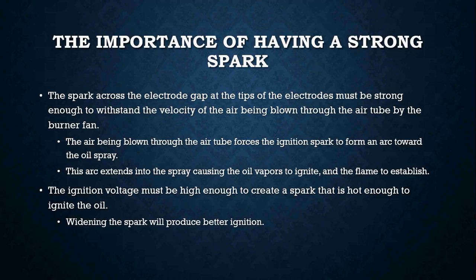Okay, the air being blown through the air tube forces the ignition spark to form in an arc toward the oil spray. So really what we want to do is use the air that's coming down the air tube to almost push that spark into that spray of oil so that we can actually ignite it. So that arc extends into the spray, causing the oil vapors to ignite, and therefore you're going to have a flame. So the ignition voltage must be high enough to create a spark that is hot enough to ignite that oil. So how do we get that heat? By applying the correct amount of voltage needed to do it.